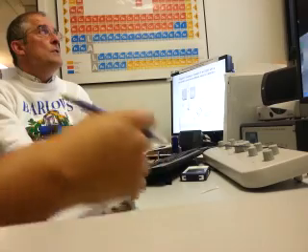All right, so you can go through these different detectors and how they work and generating X-rays and all that great stuff. This is the way you display X-ray data: spectrum plots, plotting on the x-axis the energy versus the number of counts of X-ray photons. And an X-ray map here is showing you bright spots at every spot in the raster pattern where a particular element was present, and you get to select what elemental windows you want. You can have as few or as many as the program will allow.